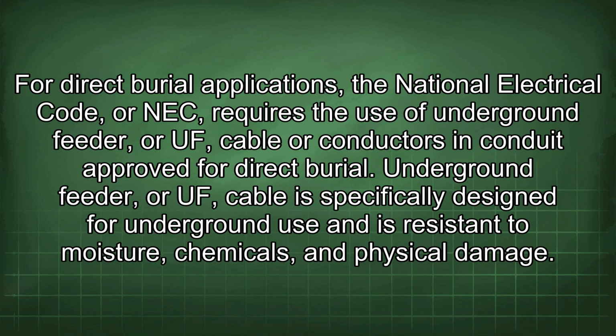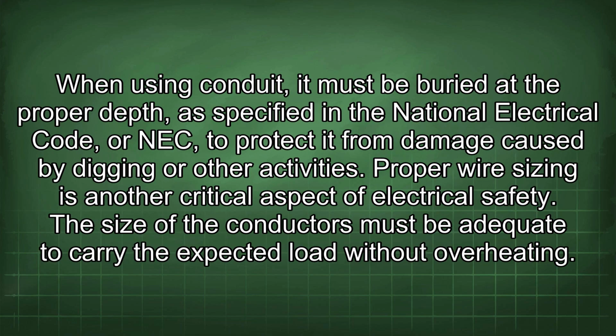For direct burial applications, the NEC requires the use of underground feeder, or UF, cable or conductors in conduit approved for direct burial. UF cable is specifically designed for underground use and is resistant to moisture, chemicals, and physical damage. When using conduit, it must be buried at the proper depth, as specified in the NEC, to protect it from damage caused by digging or other activities.